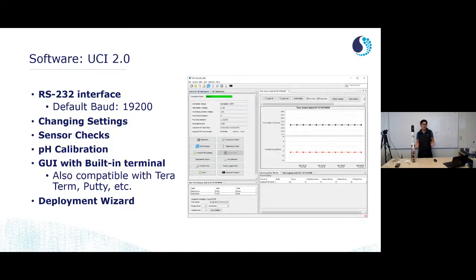So UCI, RS-232 interface, default baud rate of these instruments is 19200. And this is the software you're going to use to change settings, check your sensors to see if they're still within spec, calibrate your pH sensor, and set your instrument up for deployment with the built-in deployment wizard. This is a GUI, so there are buttons to press. Everything is kind of handled for you, but it also has a built-in terminal program, so you can send commands to this instrument just as you would to a microcat in SeaTerm. You can also use TeraTerm, PuTTY, etc., if you prefer to use a terminal.